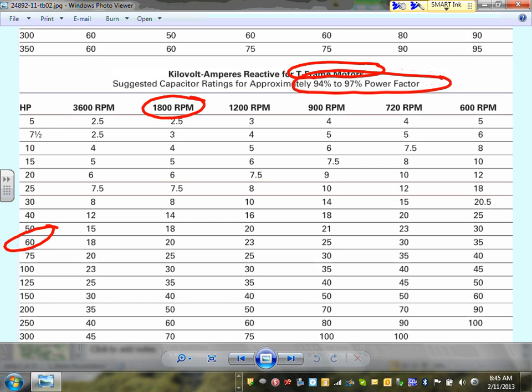Without doing any calculation, without using the table that we did before, if you go across, it will tell you the kVAR you need: 18 kVAR right here from the get-go, 18 kVAR capacitor. Can you guys see how this table works? You take the horsepower of your system. This is for 480, and this is the most common synchronous speed. From there, oops, I'm off. Am I off here? Yeah, I'm off by 1.